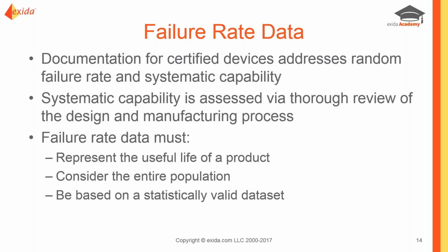It has to represent the useful life of the product. It has to consider the entire population. If it's only based on some devices, if some devices are thrown out selectively, it may not be representative. And then it has to have a statistically valid data set, enough data pulled together so that the calculations or the averages done on it are, again, representative and not skewed, because a small data set will skew.